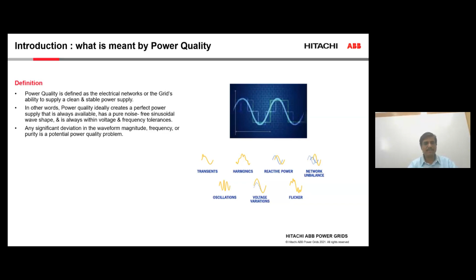Now, focusing on metro and high-speed rail for this session, we're talking about a 25 kV AC single-phase power supply for the metro rail system. Here we get lagging reactive power from traction systems, and leading reactive power from unloaded cables. That's one type of problem. Another is harmonic current generated by train rectifiers and auxiliary station loads. We also have significant unbalance since trains are single-phase loads, and frequent nuisance feeder tripping due to various reasons, which can also create a lot of disturbance.